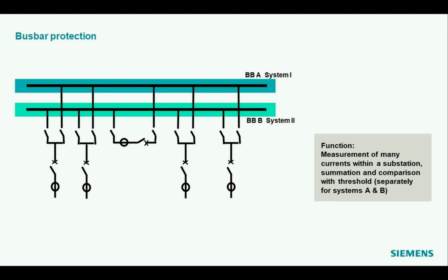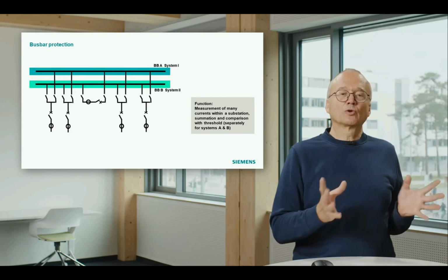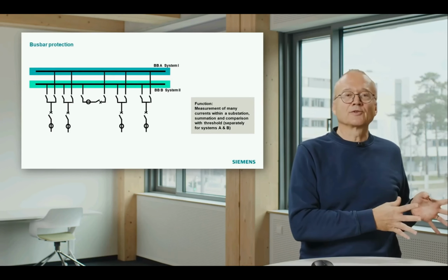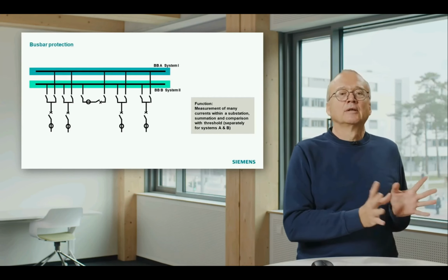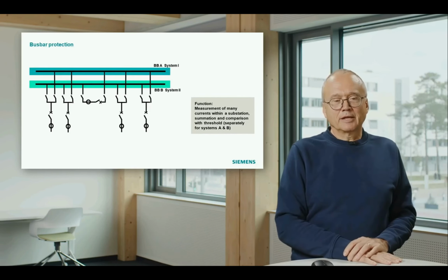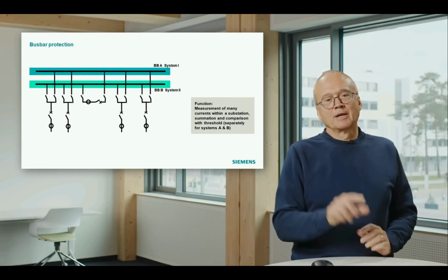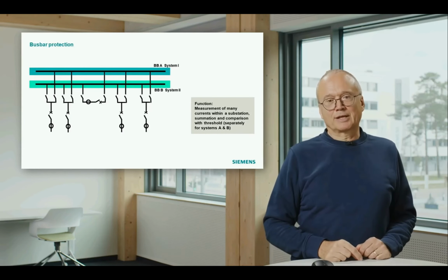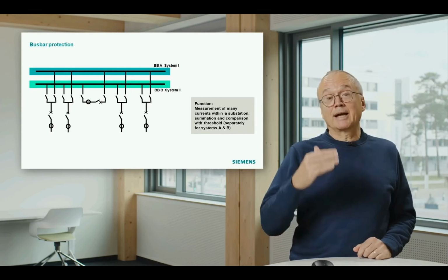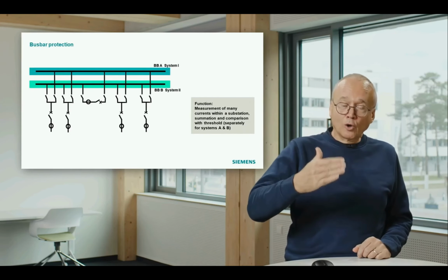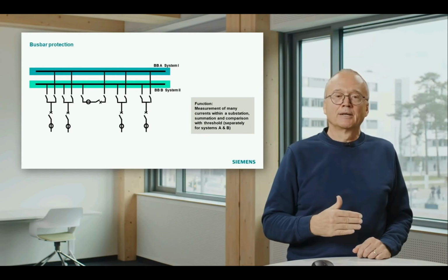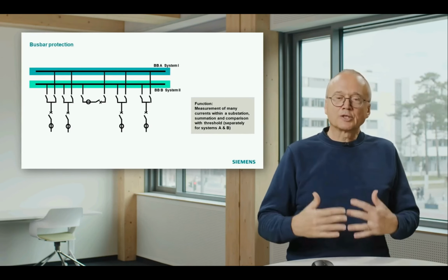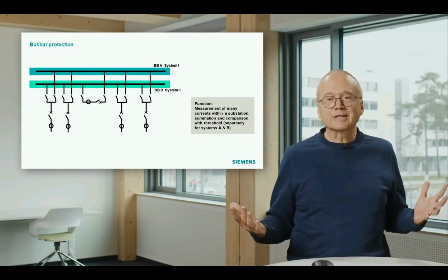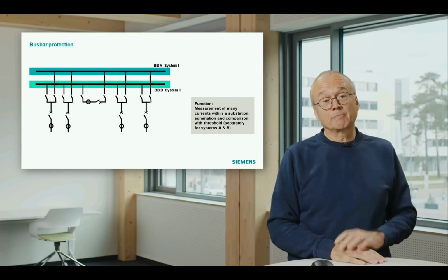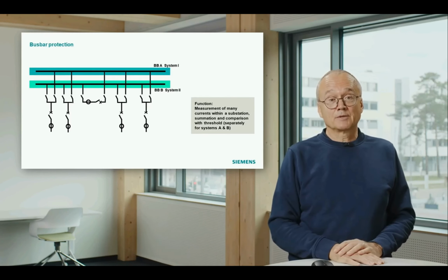And you must always have in mind, if something goes wrong in a line protection, you have a wrong trip, you lose 1 line in the system. It's not nice, but it will not be a very severe thing. If something goes wrong in a busbar protection, you lose the busbar, and that means you lose all lines connected to that busbar. That means with 1 wrong trip of a busbar protection, you may lose 10 lines in your system, and that can produce already a critical system state.